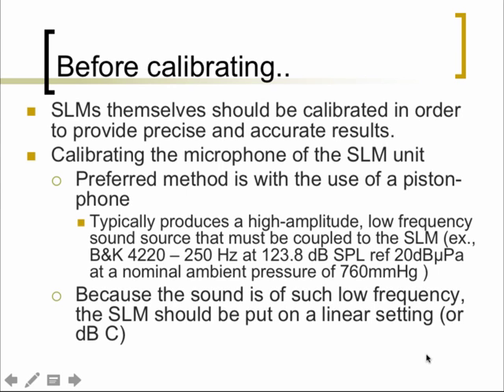Even before using your sound level meter for audiometer calibration, the sound level meter itself needs to be calibrated. An engineer would bring along a standard sound generator — often known as a piston phone or calibrator phone — which produces a very consistent output amplitude at a certain frequency. For instance, the B&K 4220 piston phone emits 123.8 dB SPL at 250 Hz under normal pressure conditions.